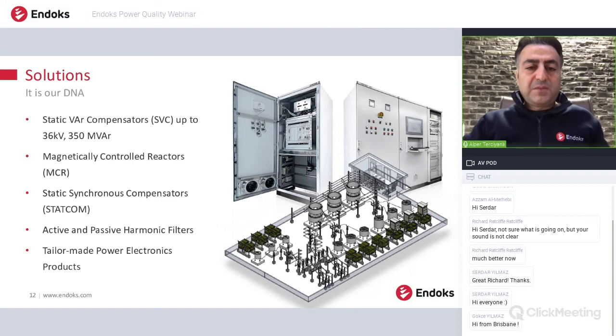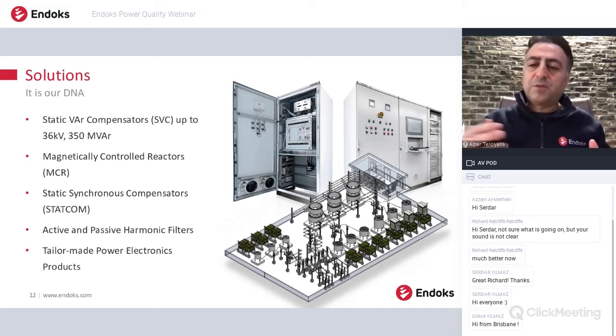So what would be the solutions for these problems? Of course, there are many solutions for each type of power quality problem, like SVCs, magnetic control reactors, STATCOMs, static synchronous compensators, and active and passive harmonic filters. But especially on the medium voltage network, each power quality problem is very special, and you have to find a solution for each specific problem. So the solution is a tailor-made solution at the end of the day, because the network parameters and the load parameters all affect the solution, and you have to design your solution based on this information. That's why, especially for medium voltage, the power quality solution at the end of the day is a tailor-made solution.